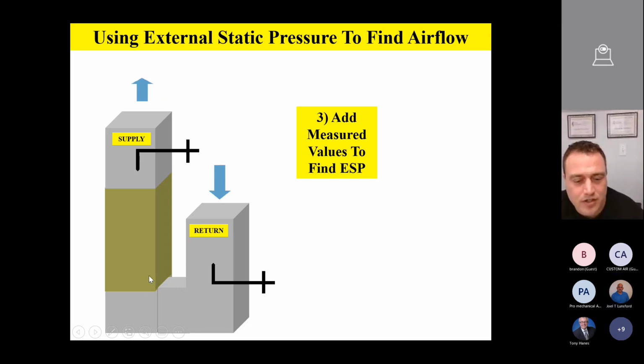So you want one in the coil, or do you want one by the blower? In your scenario, are you going by a blower that's at the bottom, like a positive? All right, so let's say, for instance, in this air handler right here, look at my cursor, let's say we have the coils right here, and then the fan is below the coil. Then just poke a hole in the cabinet so that you're reading the maximum suck of the fan. And that's why they're a little confused, because most of our air handlers are negative, so you're going off a positive, right?